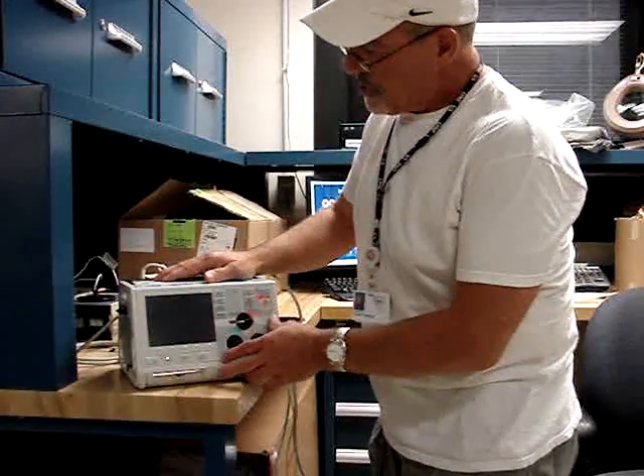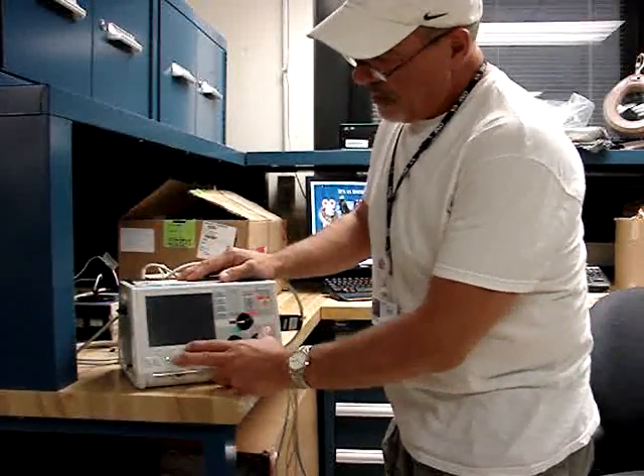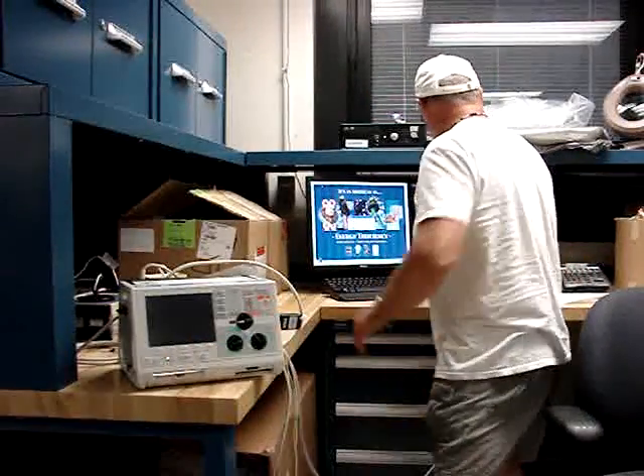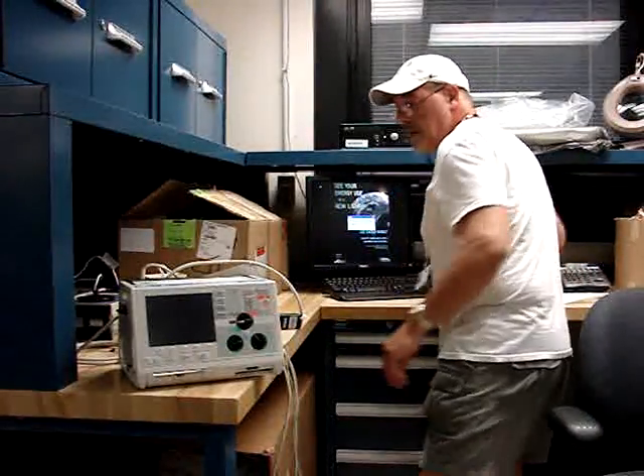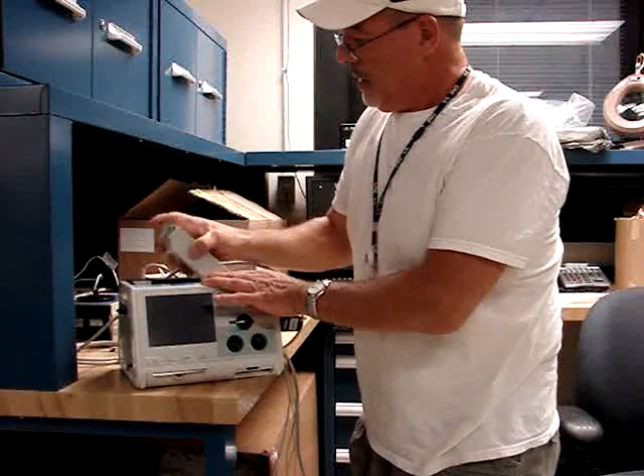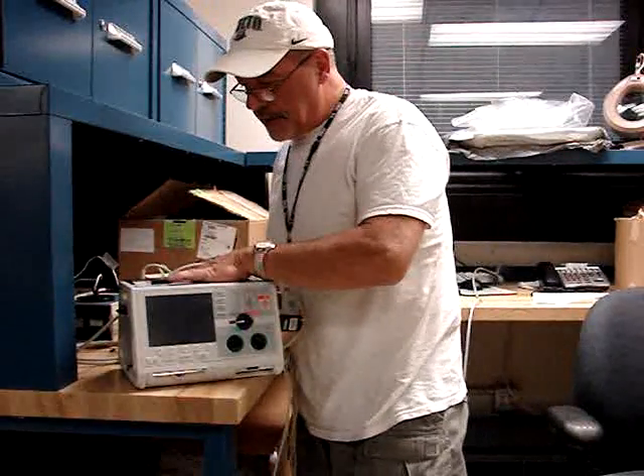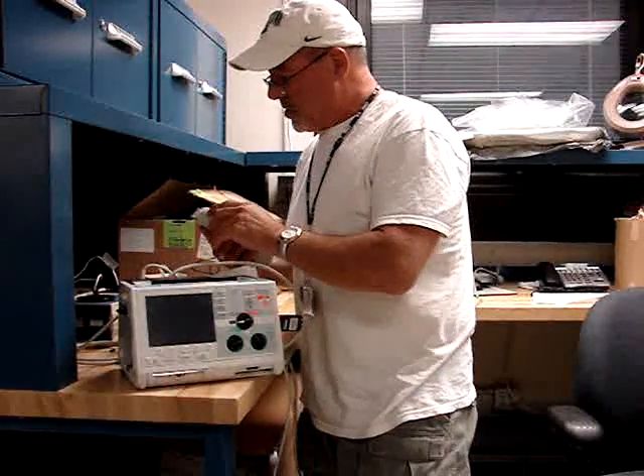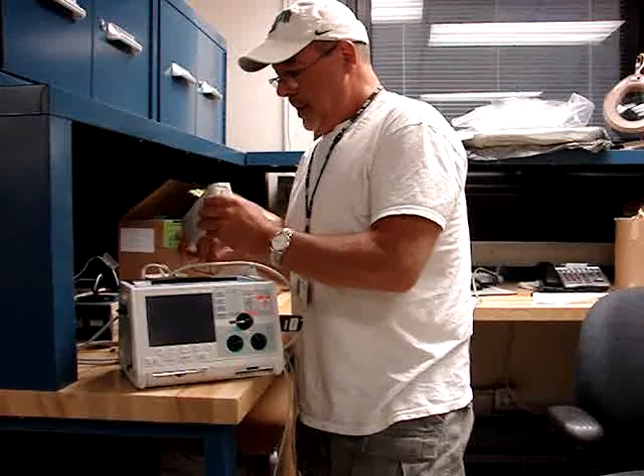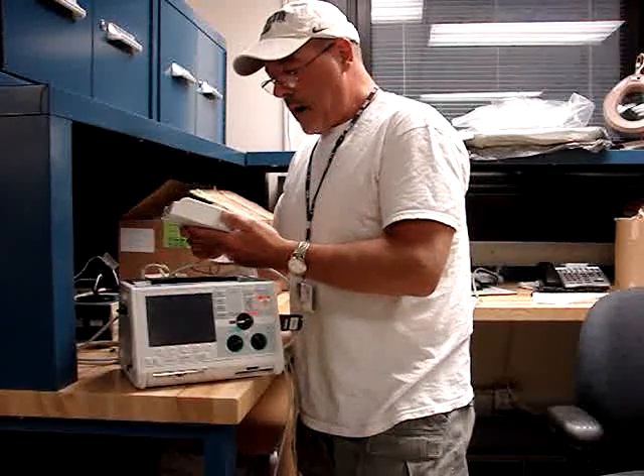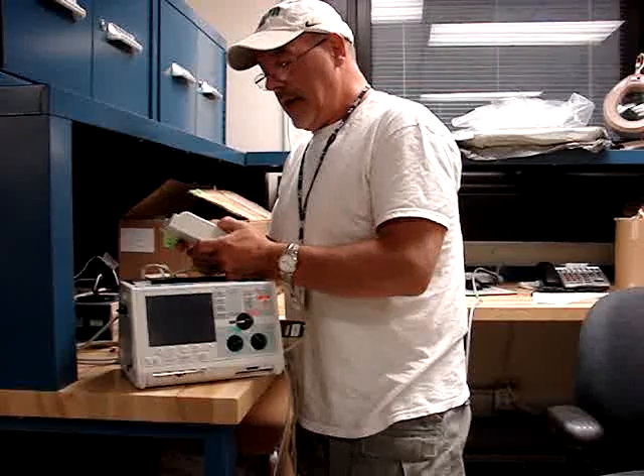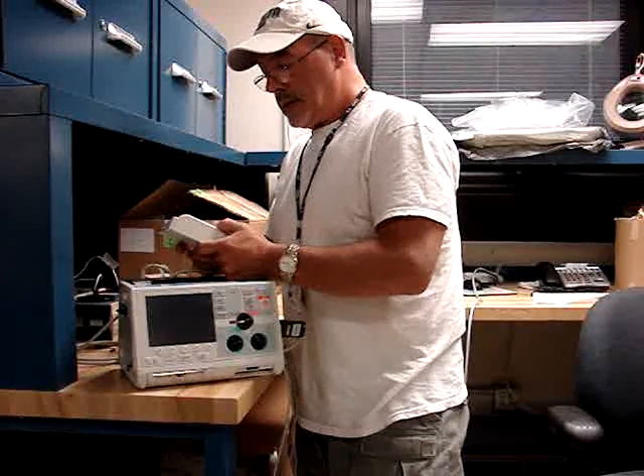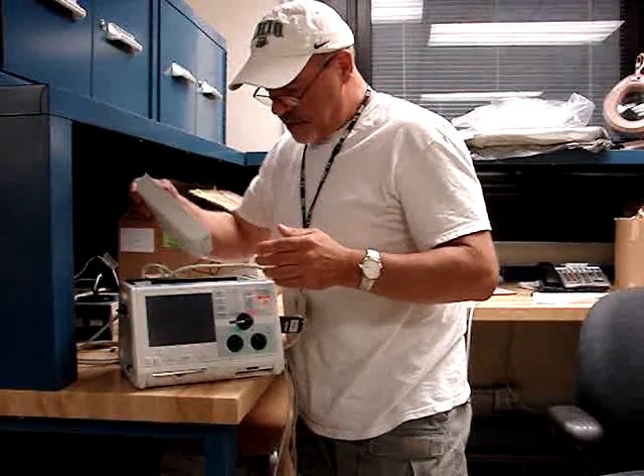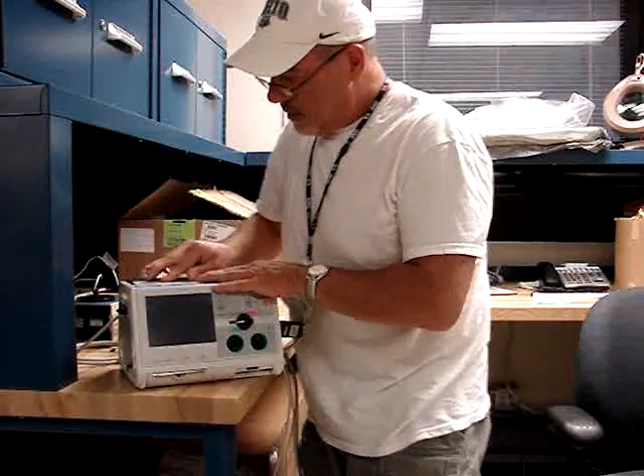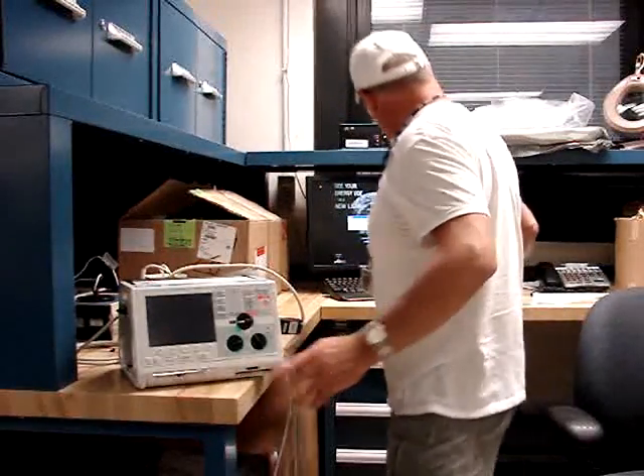Okay, this step we're going to check the batteries for condition. Got the light on, so we're going to unplug it. Make sure it's off. Remove the battery, check the housing, check the connectors inside, make sure they're okay and they look good. Battery shows no signs of wear, cracks, and our test date is good. So we're good till August of this year. So we can install that. We'll plug it back in.